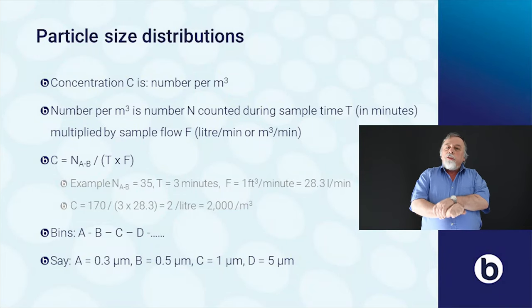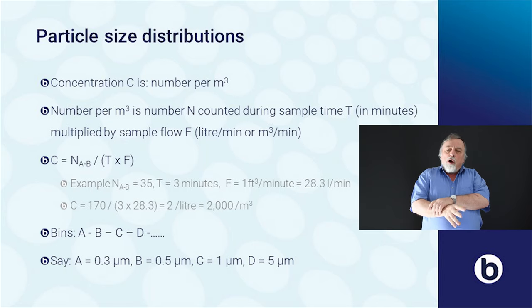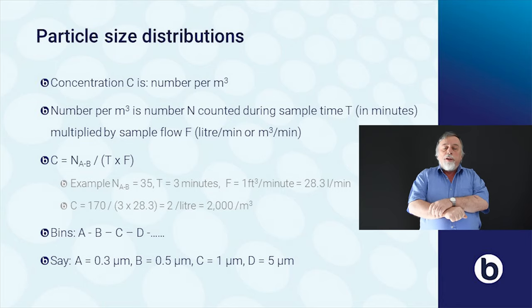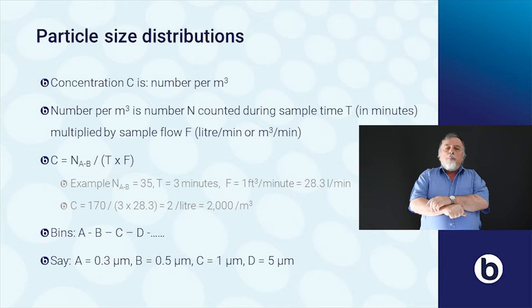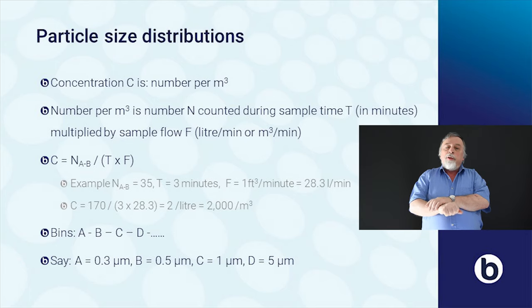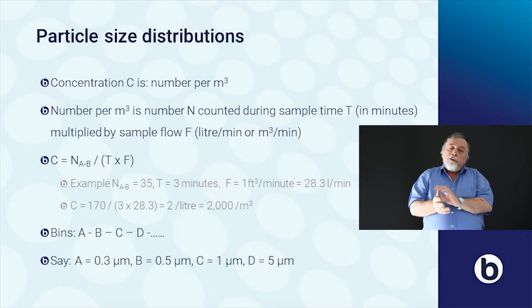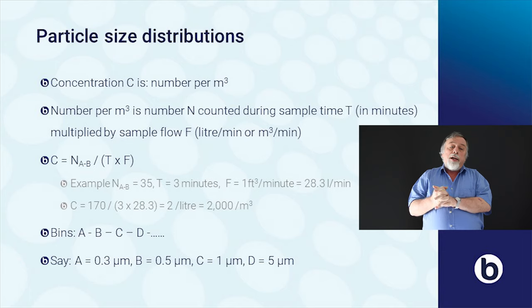With a particle counter we measure the concentration, which is the number of particles per cubic meter. Often these counters measure per cubic foot, but we calculate it into cubic meters to be able to compare measurement values with ISO standard limits. The number of particles per cubic meter is found by taking your sample time in minutes and multiplying this by the sample flow in liters per minute or cubic meters per minute.